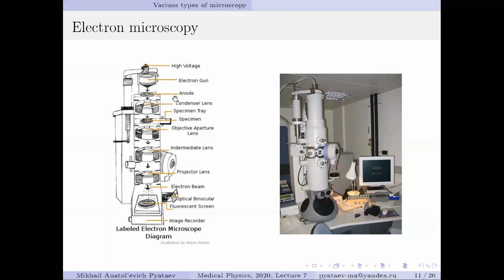So this anode is the part of device which accelerates electrons, so the high electric voltage is applied between this electron gun and anode, and it also focuses. Then the beam is focused by a so-called condenser electrostatic lens, and the focused beam goes to the specimen.